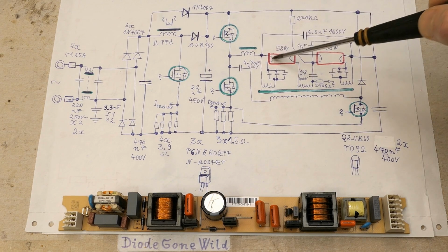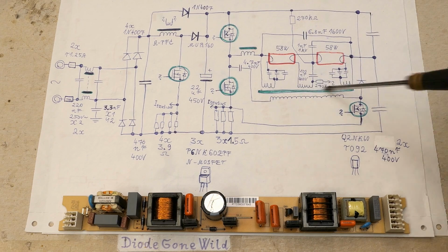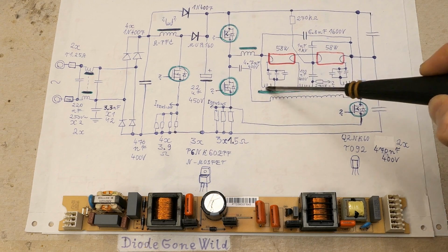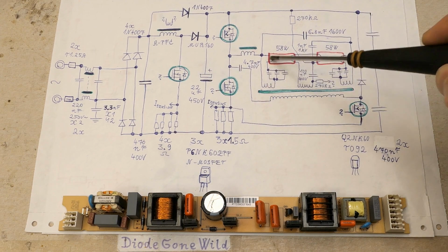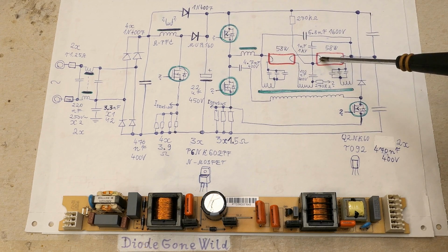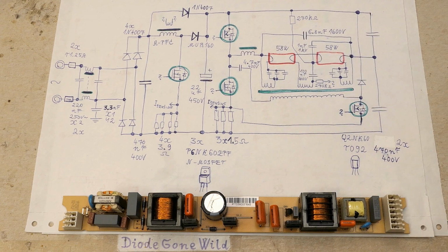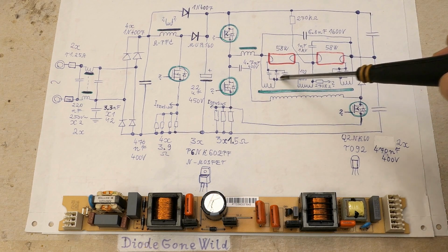Initially the cathodes are preheated using this preheat transformer with 3 secondary windings. This one heating this filament, these two in series, and this one for this filament. The filaments are connected via some capacitors.